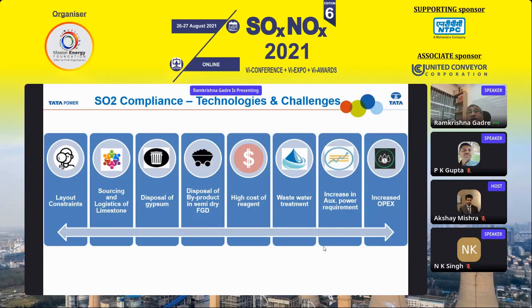But if we already have a dry system like hydrobin or a total dry system, then disposing of this wastewater becomes a quite difficult job, because the TDS being guaranteed is more than 30,000 to 40,000 with very high chloride. In fact, in the USA, people are now choosing dry FGD because of these issues, because dealing with this wastewater and putting up a ZLD is again a cost requirement. For a 1,000 megawatt plant with 30 cubic meters of water used, such a new ZLD for FGD may require some 60-70 crore. So this is a challenge people may start facing once they get into more detail about wastewater disposal.